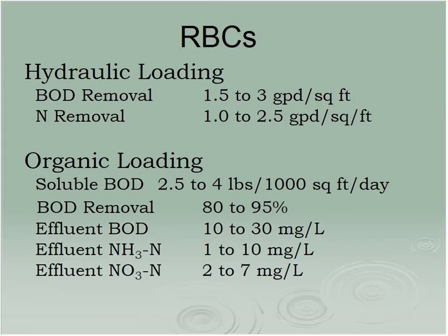They do 80-95% BOD removal, do very well. You can get your nitrogen down fairly well. They downsize quite well. You generally don't see them in plants greater than 3 million gallons a day. I went to the Charlton rest area on the turnpike. Right up behind there is their treatment plant, and they're all running off RBCs.